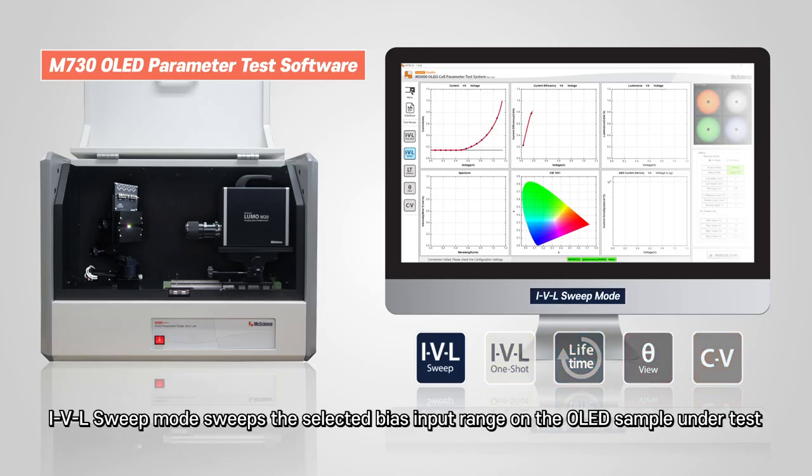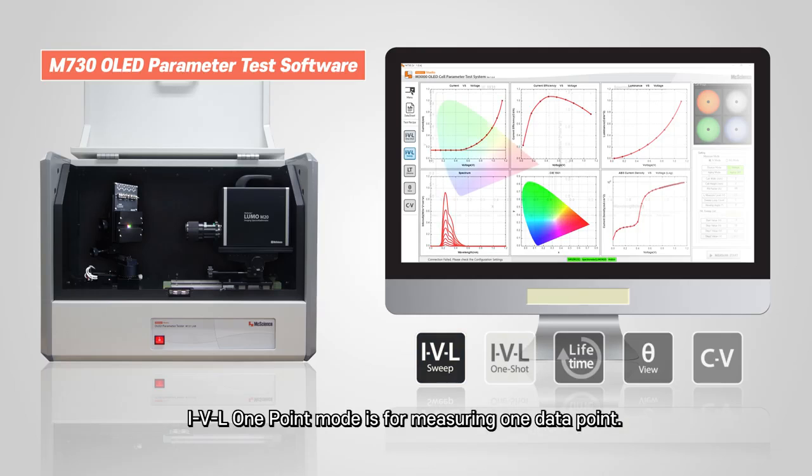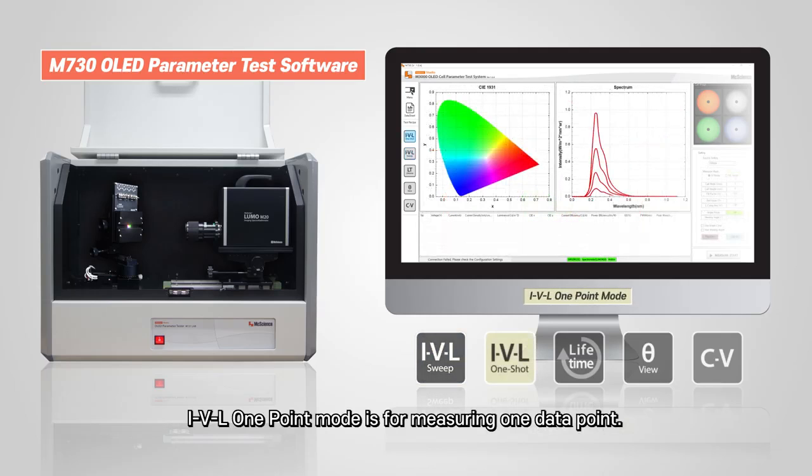IVL sweep mode sweeps the selected bias input range on the OLED sample under test, while measuring and recording the luminance data for each sweep point. IVL one-point mode is for measuring one data point.